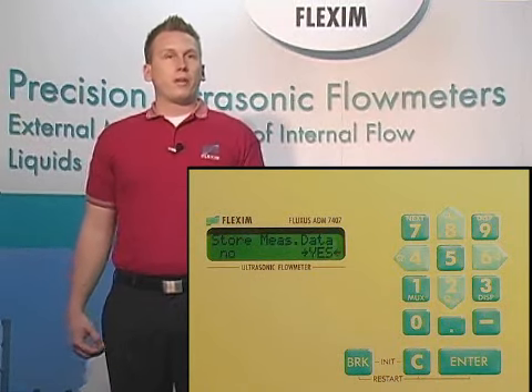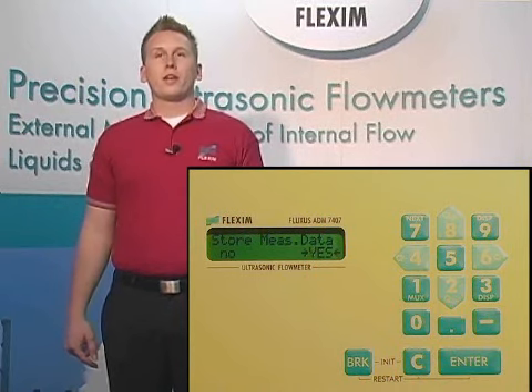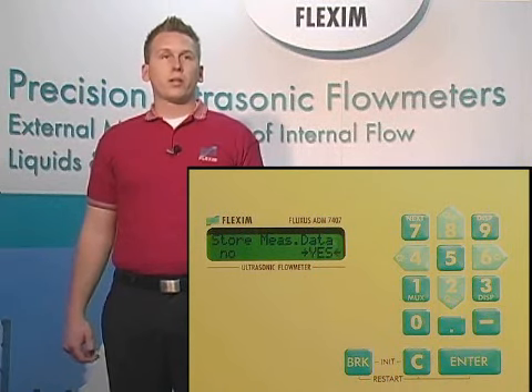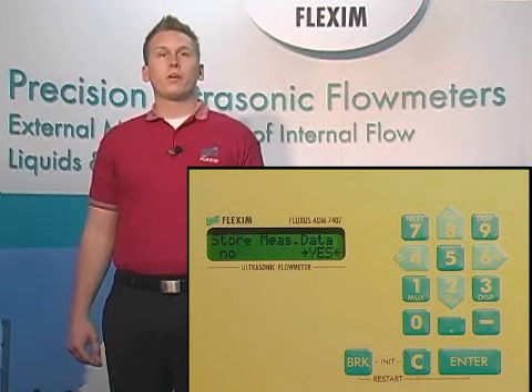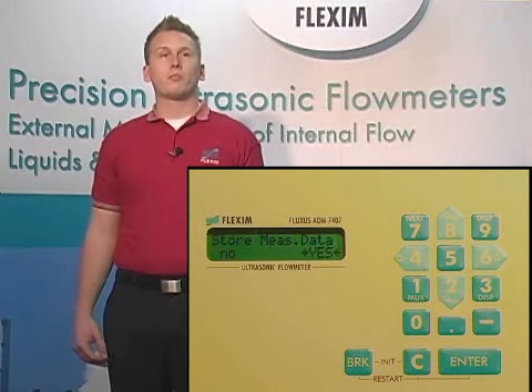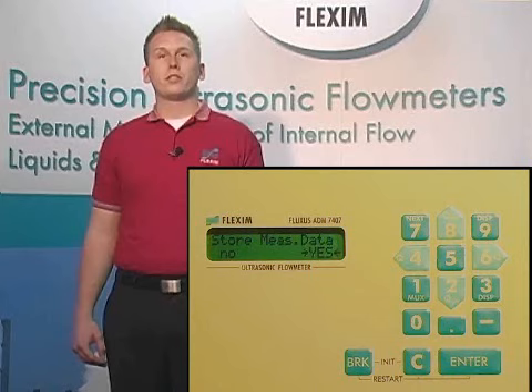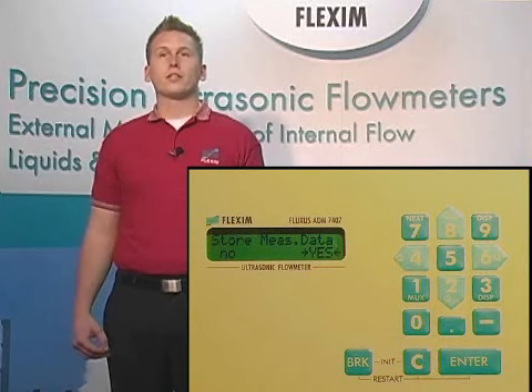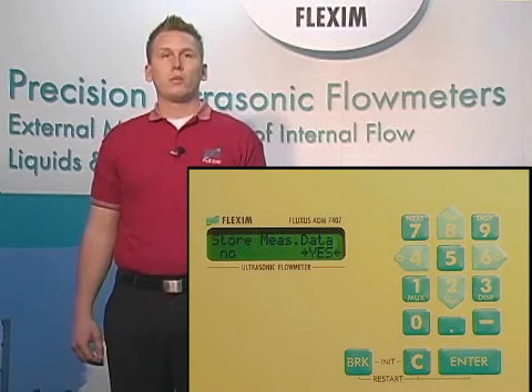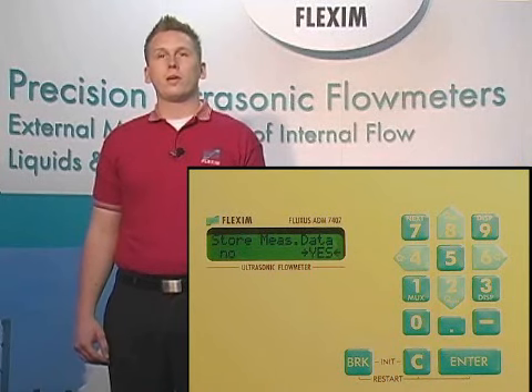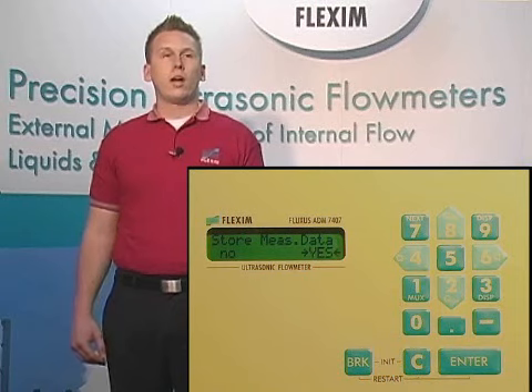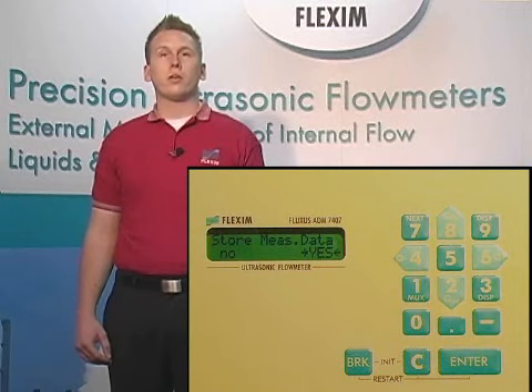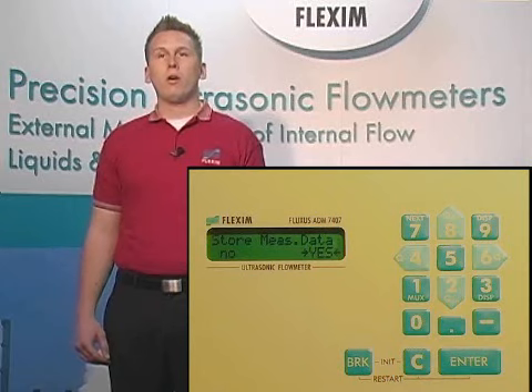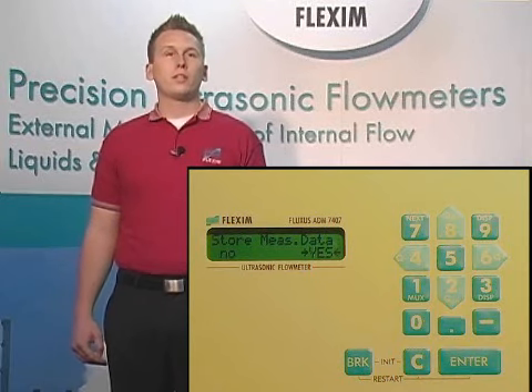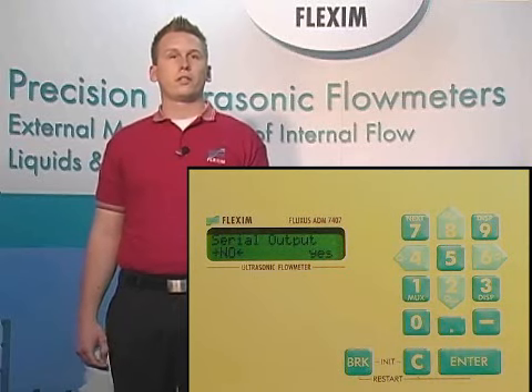This next option is very important. We have several different ways of taking information out of the meter. We can simply look at the display, we could take a 4 to 20 milliamp signal out to a PLC, or we could store data in the meter itself in our 100,000 point internal data logger and retrieve the information to view on a computer at a later time. This is the purpose of store measured values. We generally recommend to keep this turned on since there is absolutely no downside in doing so. However, if for whatever reason you would choose to turn this off, we could simply scroll left over to off to disable it. For now though, let's leave this as the default of on and hit enter.